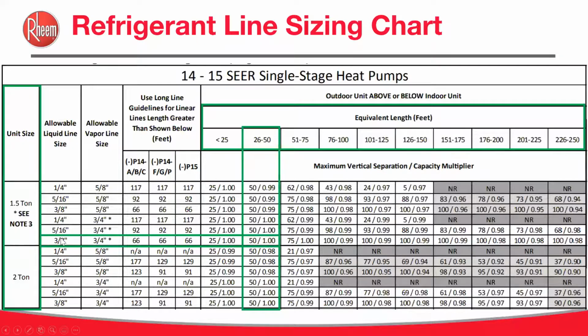And in this situation, what we've done is we said, okay, we're going to do 3/8 and 3/4. There's an asterisk, and we're going to talk about why that asterisk is there. We go all the way across over to here. And we want to know what these numbers mean, 50 and 1. So what it means is if I use 3/8 and 3/4, I can do a 50-foot maximum vertical separation, and I will still be running at 100% capacity.